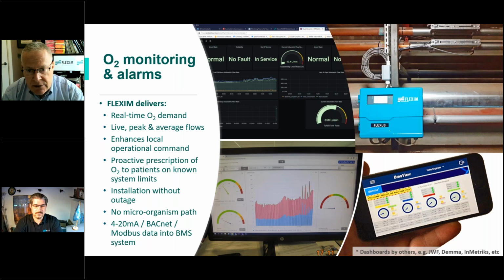Very often these systems have enough capacity, it's just that the way they were configured, there are bottlenecks in the system. And again, by having the metering, you can find the bottlenecks and you can more effectively distribute the oxygen. The installation is done without any outages, so there is never any supply interruption to the hospital patients. And of course, because it's not breaking into the line, there are no microorganism paths. We're not introducing any areas where bugs can collect.